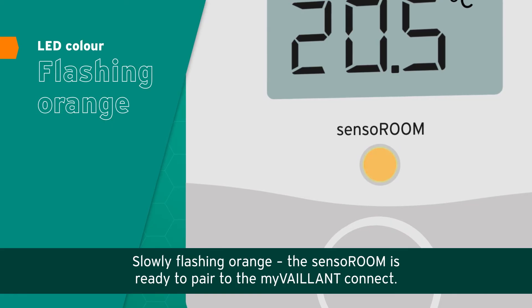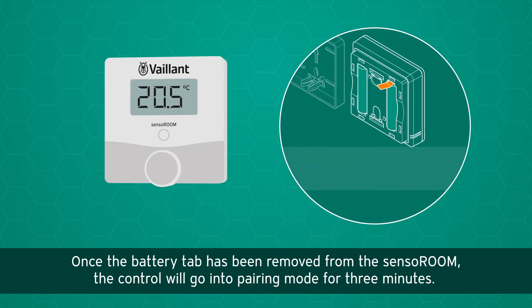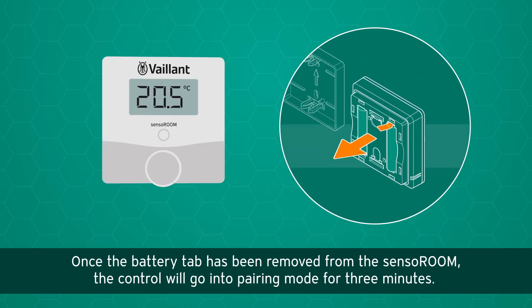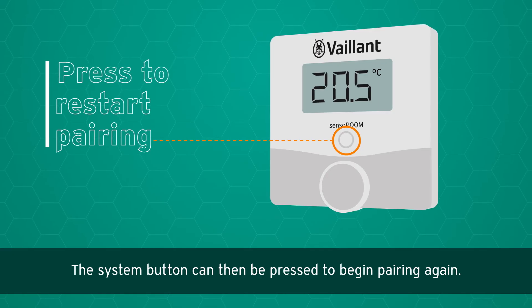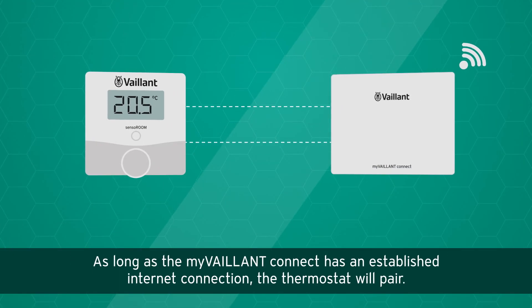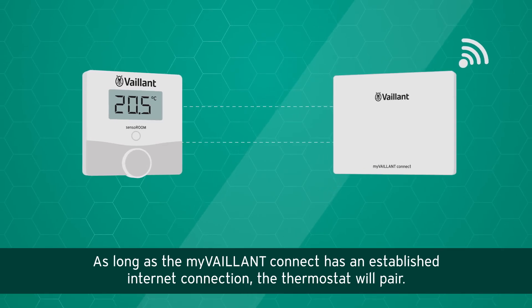Slowly flashing orange means the sensoROOM is ready to pair to the myVAILLANT connect. Once the battery tab has been removed from the sensoROOM, the control will go into pairing mode for three minutes. The system button can then be pressed to begin pairing again. As long as the myVAILLANT connect has an established internet connection, the thermostat will pair.